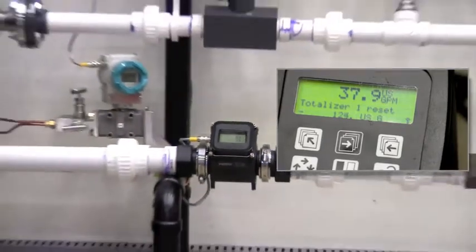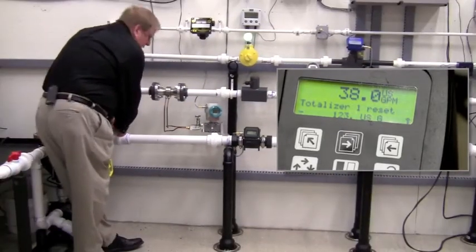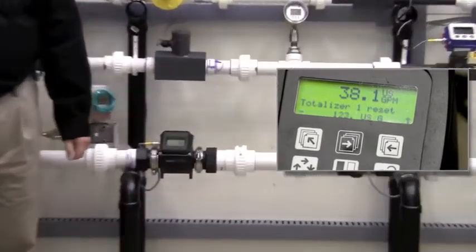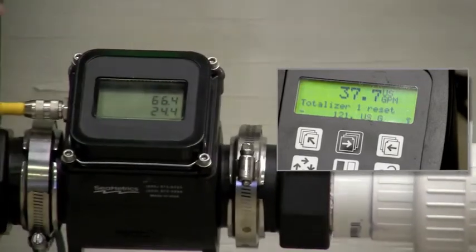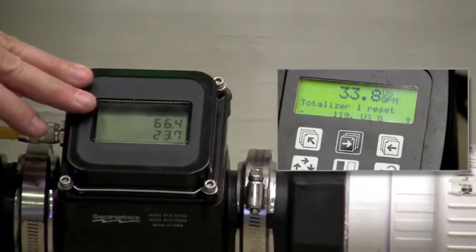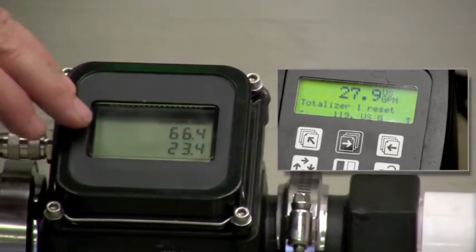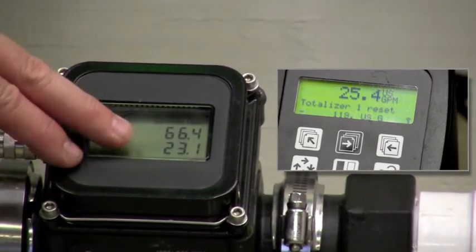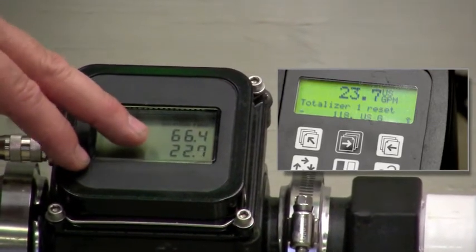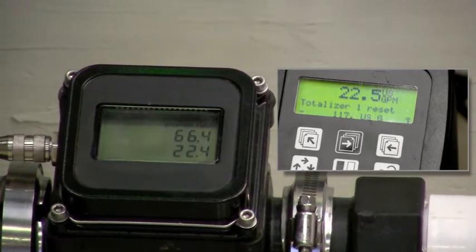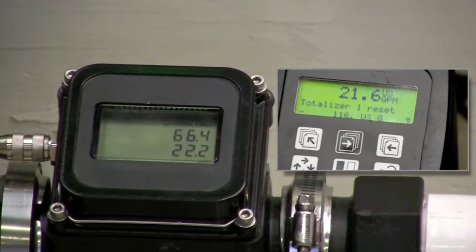Now I'm going to throttle the valve back a bit to reduce the flow in the line and again we'll give it a second to settle in. You can see that our WMP, the flow has dropped to about 22-23 gallons a minute and it tracks right along with the high performance mag.